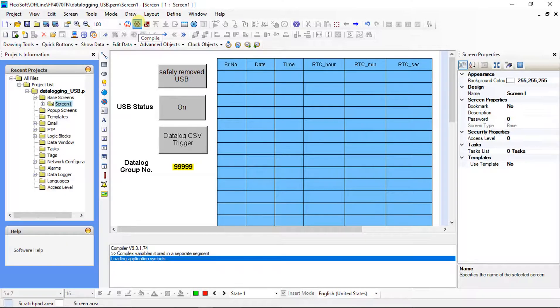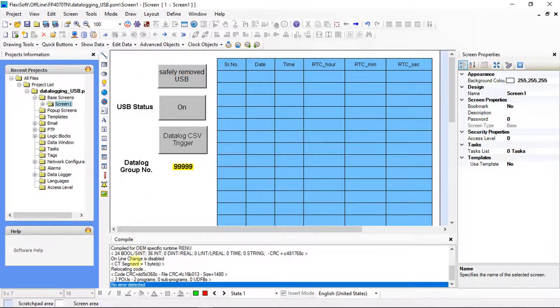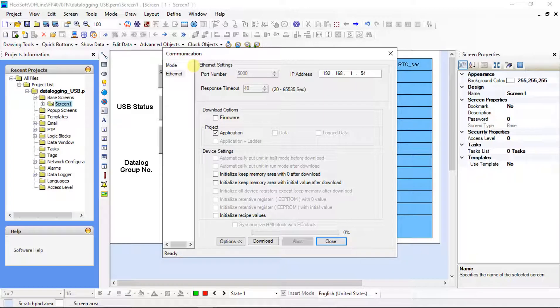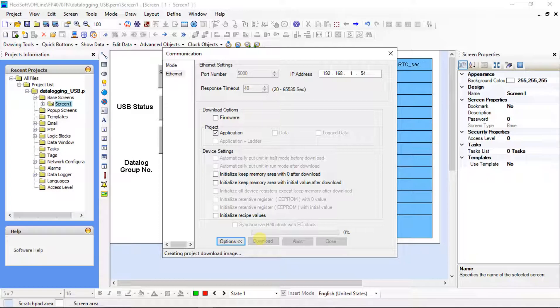Compile the project. No error detected, so we can proceed to download. Click on the download icon. Communication window is on screen — here Ethernet will be used for downloading the project. Write the IP address of the device network. From download options, click on application from project, then click on the download button. Now downloading is done — close the screen.